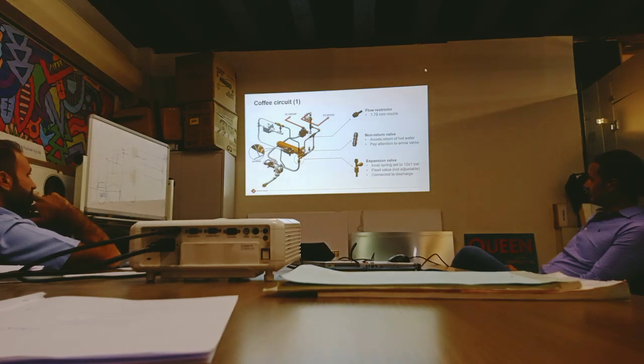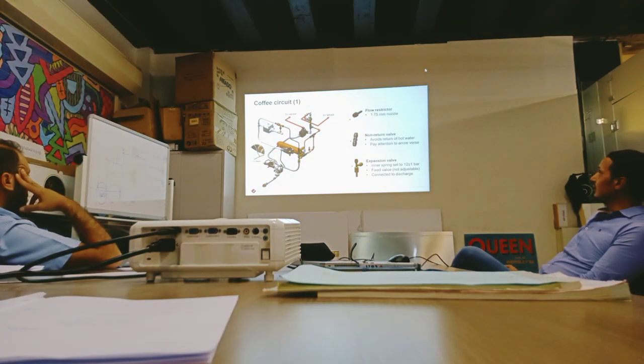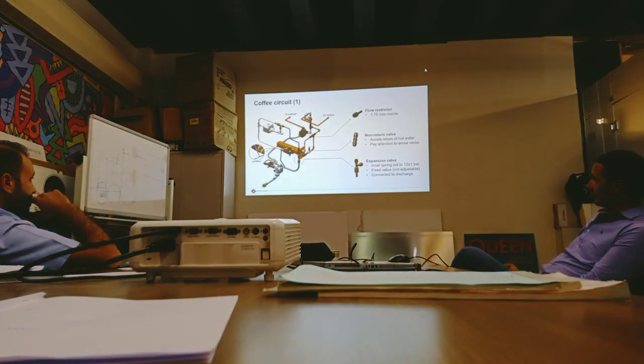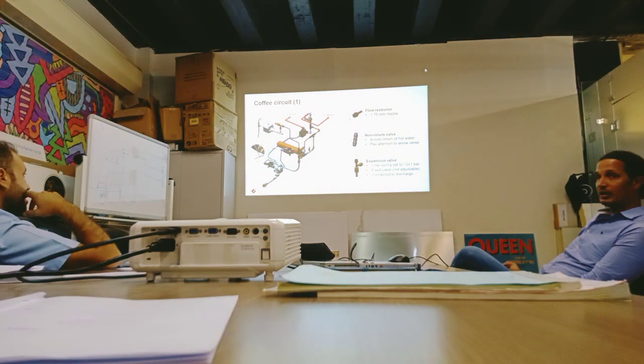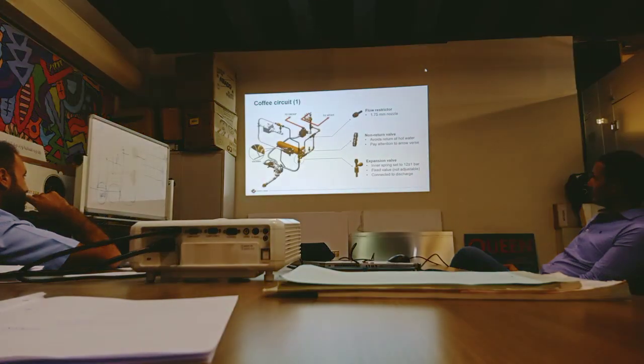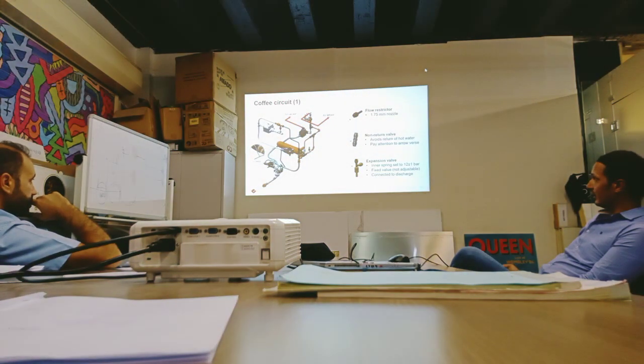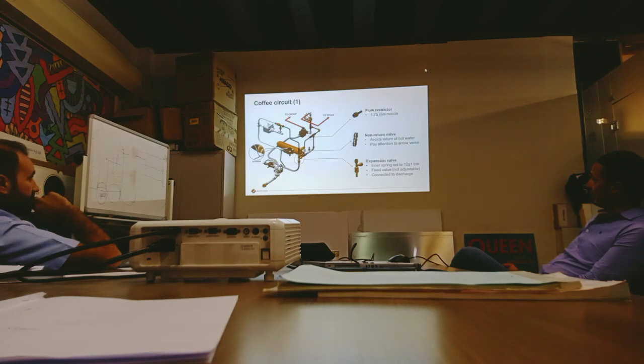After the expansion valve, the water takes its way to the pump. Here to the flow means from the pump to the expansion valve. After the expansion valve, we go to the heat exchanger. From the heat exchanger, the water comes out hot, and here there is a T connector and the mixing point. Before that, there is a flow restrictor with a 1.75 mm nozzle. From the other side is the cold water, and this is the regulator. They can adjust the mix. The mixed hot and cold comes here to a T connector. From the T connector, if we follow this way, we go to the group valve.